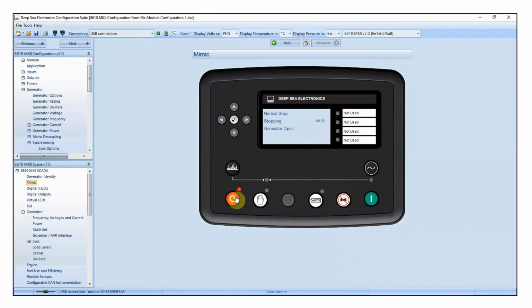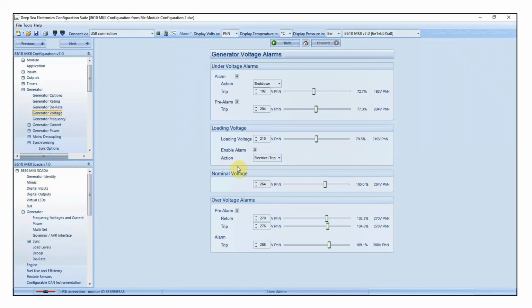And then just like we did with the governor, we're now going to decrease that nominal voltage by 10%. This would be 216 for my application. And write that back to the controller. Just like before, you'll start the generator, it will still run its nominal voltage, in my case, 240 volts. But then as soon as we tell the DSE module to close that genset breaker, the nominal voltage will then start to decrease down to that new nominal setting of 216.